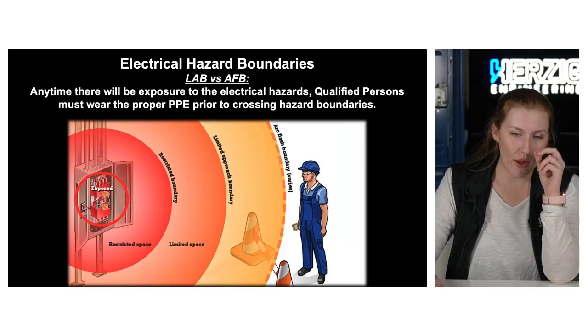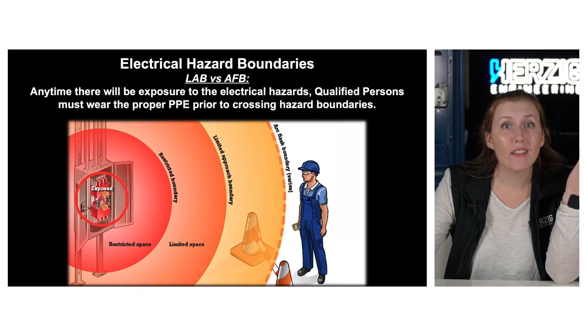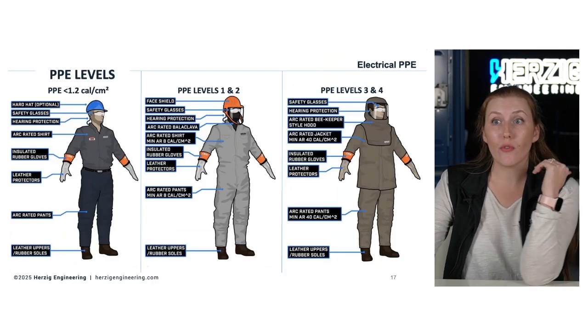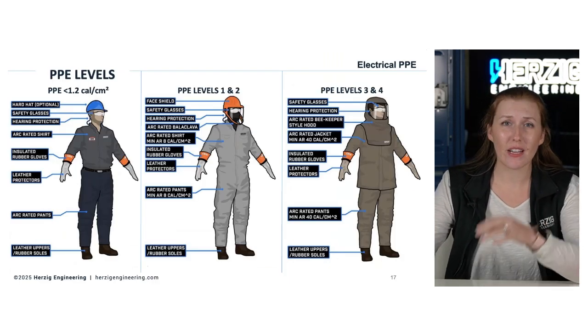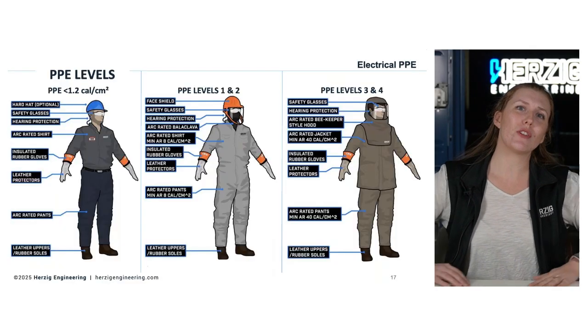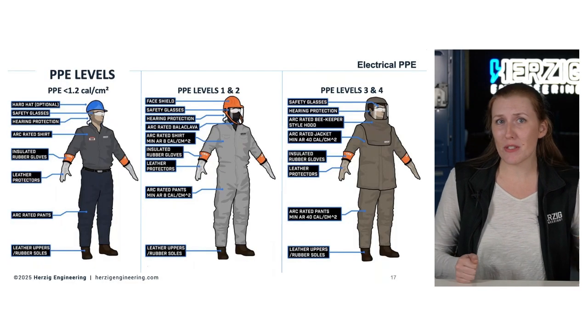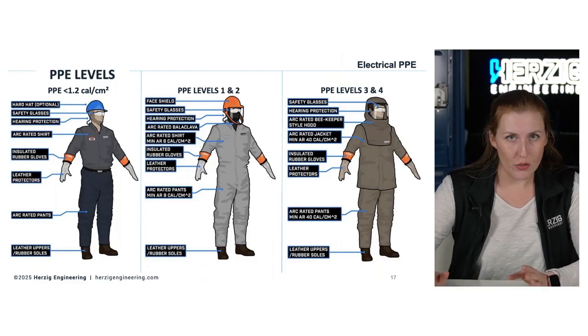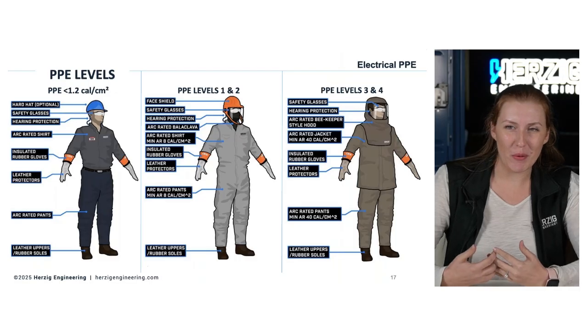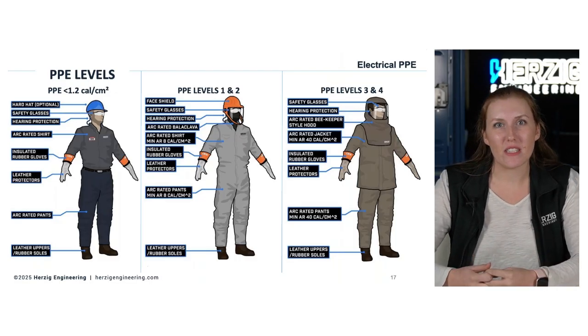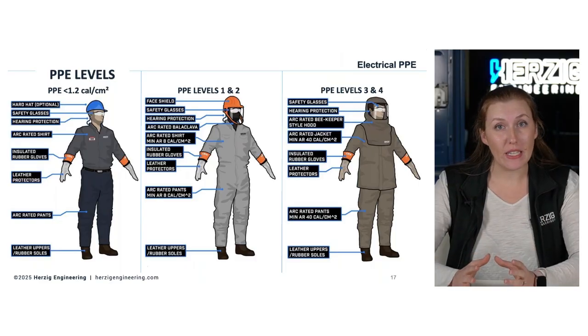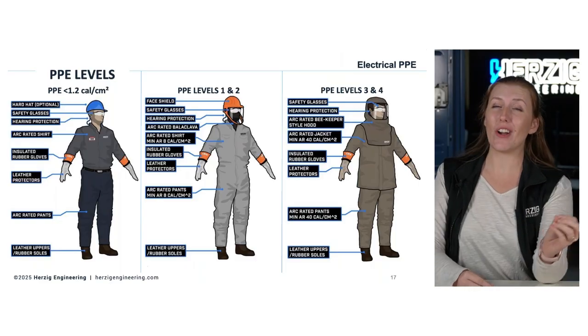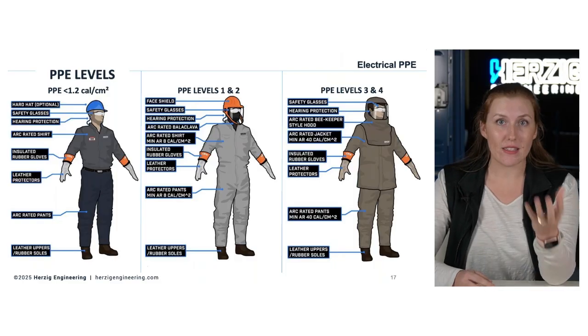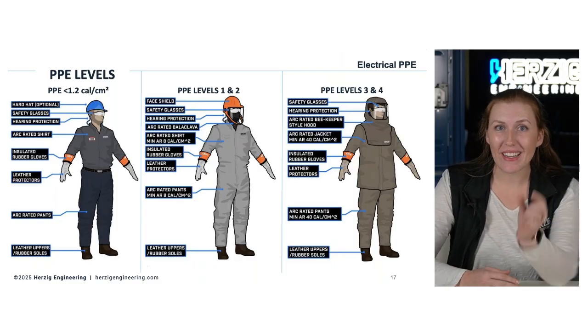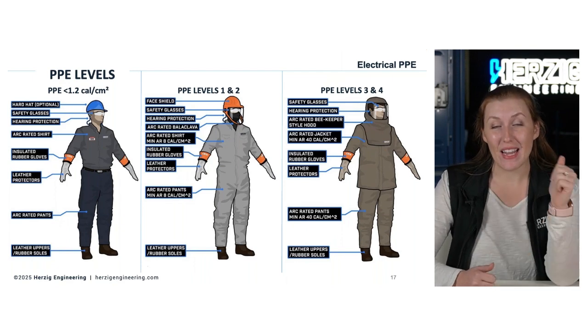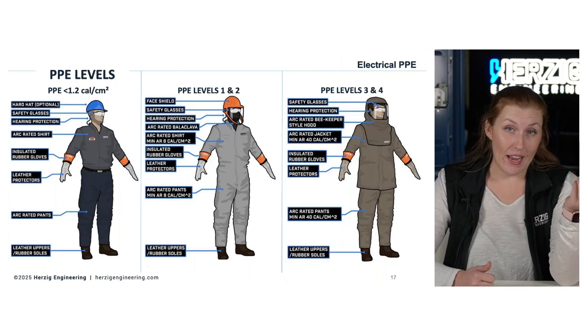Now, the other reason they're not wearing the proper PPE is maybe they just don't know what it is - missing elements of it, or they go for that 40 cal suit every time and get tired of wearing it, so they think, for this quick simple task I'll just skip it, don't mind me. All those little phrases are huge red flags and speak to a human performance issue. You've got to have the self-discipline to stop and ask: what PPE do I need, do I have all the elements, and are they in good working condition? So again, as far as working without proper PPE, the keyword is proper - is it rated properly, is it maintained well and in good condition?